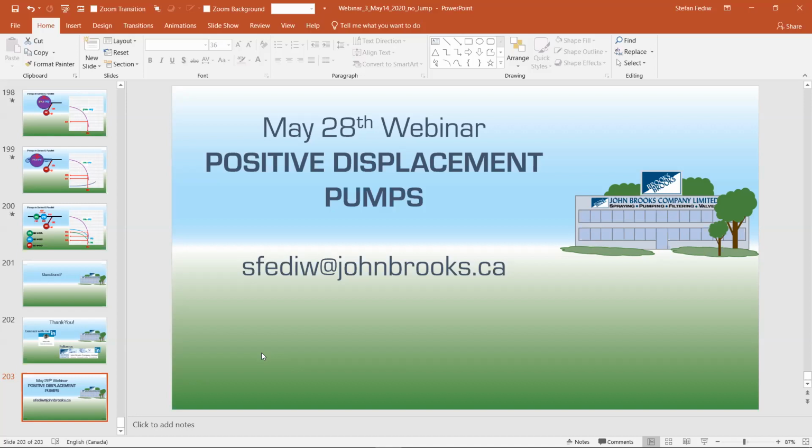We see a more galled or plasticine kind of smooth hit, and so it doesn't look as bad. But the forces are still going to be the same. Those forces are still acting on the bearings, on the mechanical seal, on the shaft. So eventually, it doesn't make a difference what material is taking the impact. Your whole drivetrain is taking the abuse.